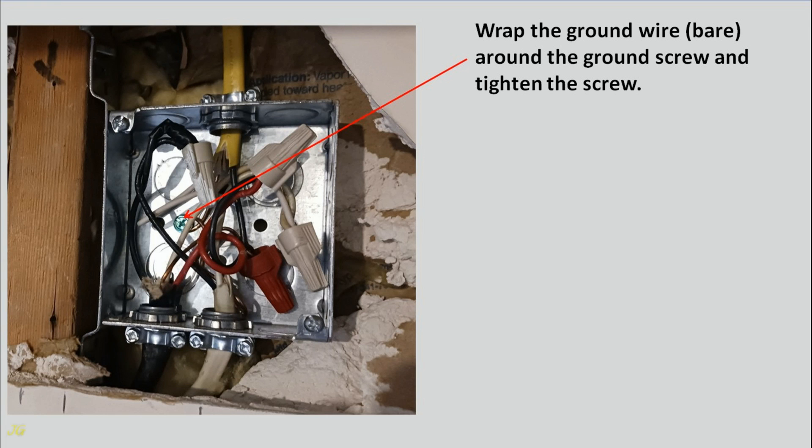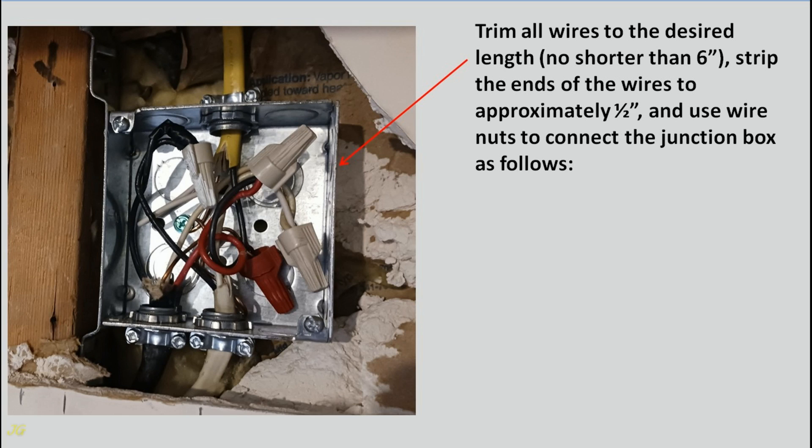Wrap the ground wire bare around the ground screw and tighten the screw. Trim all wires to the desired length, no shorter than six inches. Strip the ends of the wires to approximately one half inch and use wire nuts to connect the junction box as follows.